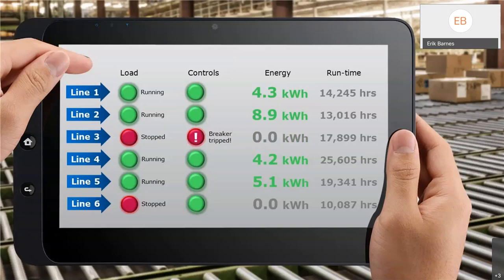Let's say on line 3, there's a breaker trip, right? We can sense that with Island. We can sense there's no voltage on the line side of the starter terminals, and you get a notification, you get that alarm. So you can alert the operator: hey, you had a breaker trip on line 3. Well, that's great. Now the operator knows there's an issue on line 3. It's a breaker trip, likely related to a short circuit type of issue. So let's call maintenance, right? Let's work around this, focus on the problem and get it resolved.